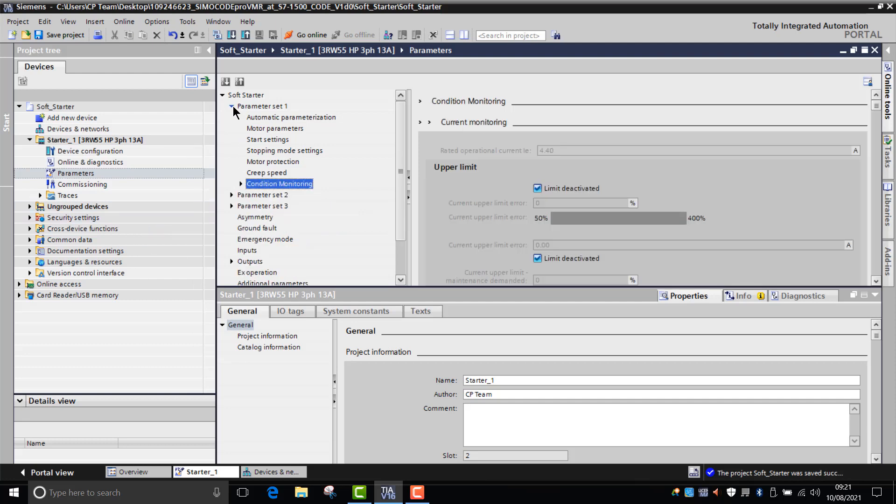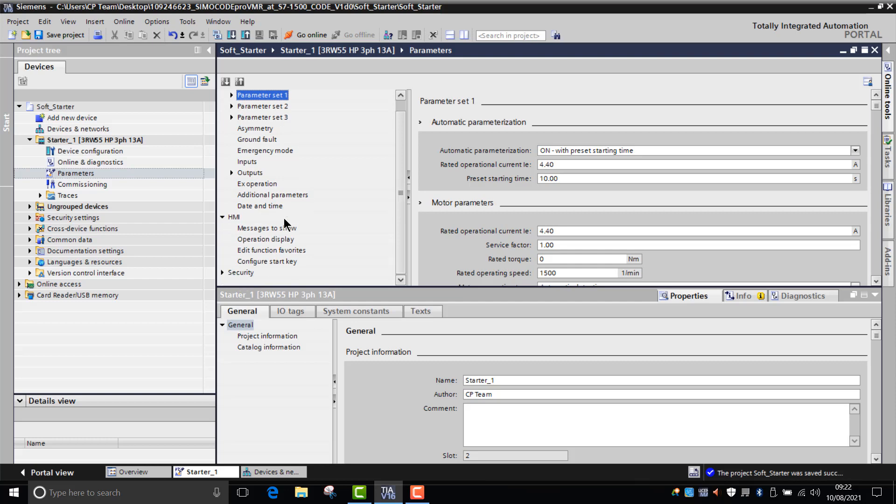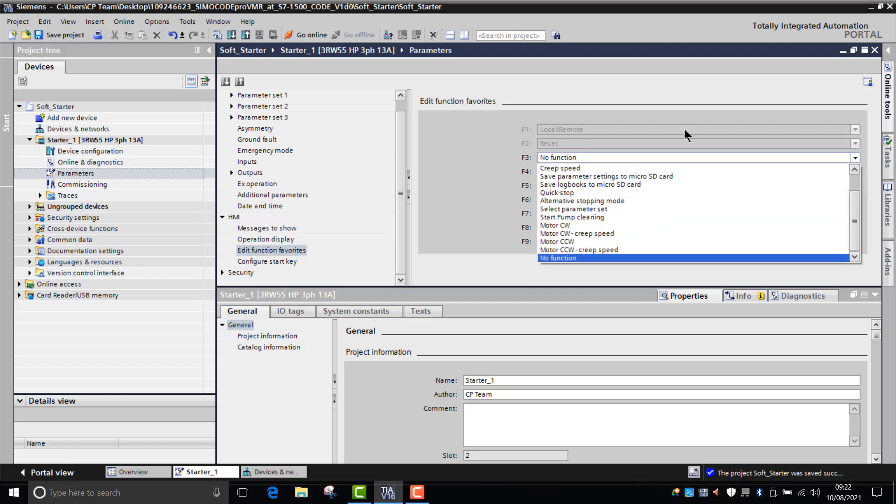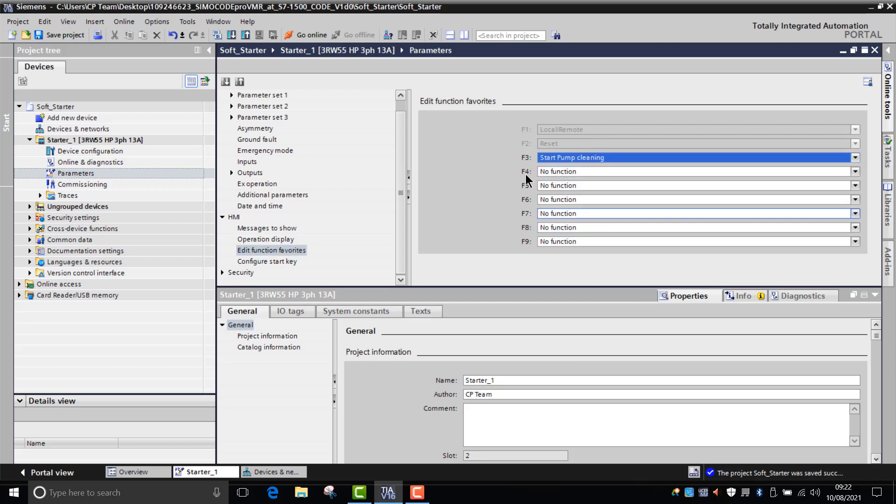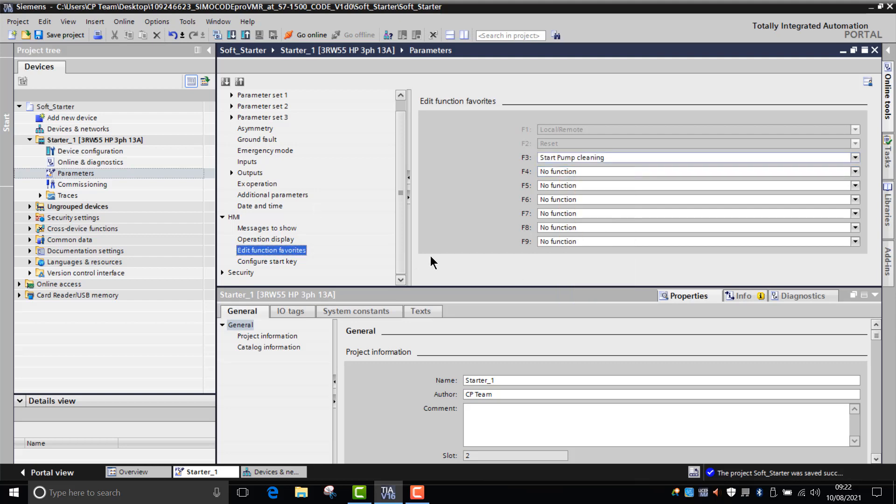One of the favorite ways of doing it is by accessing that through the local HMI. If you go into HMI commands, you can edit the favorite keys. At the moment it's got F1 and F2 which are already input as being switching from local and remote and reset, but you can change F3 or one of the other keys to the pump cleaning mode. If you press F3 on the HMI, it will then start the pump cleaning function.